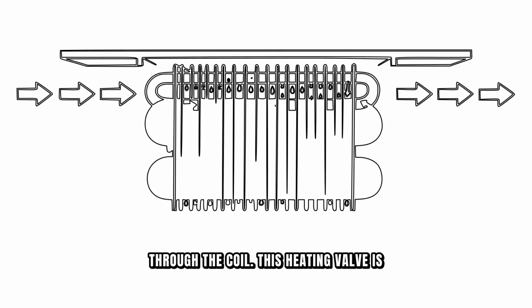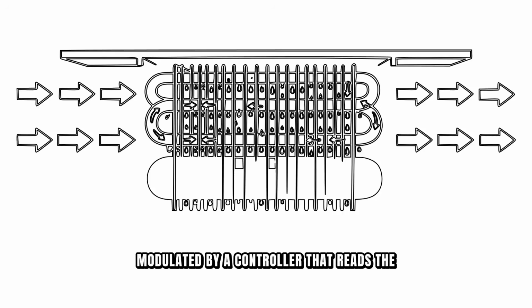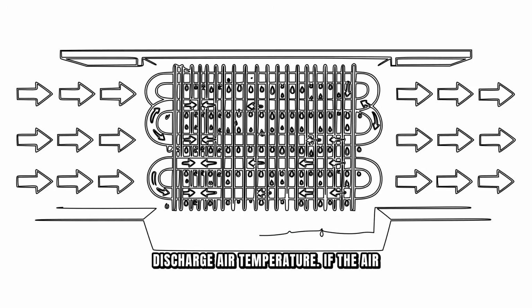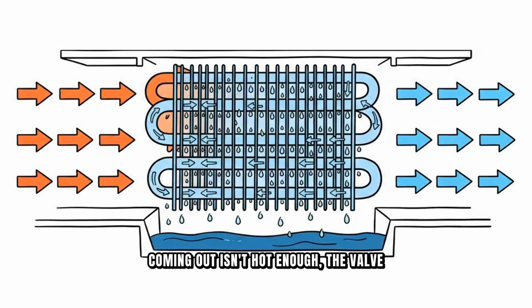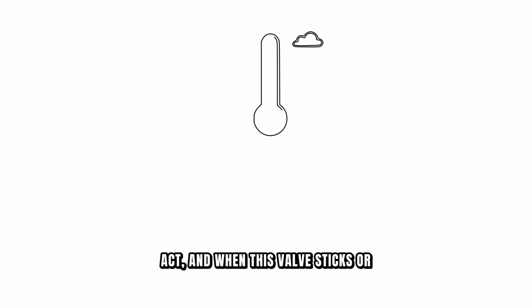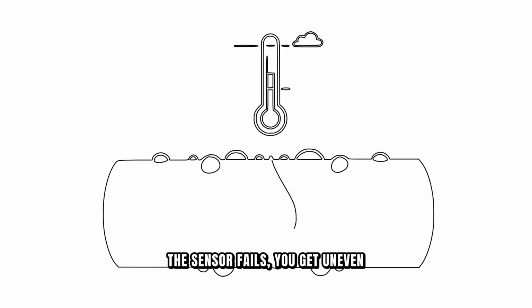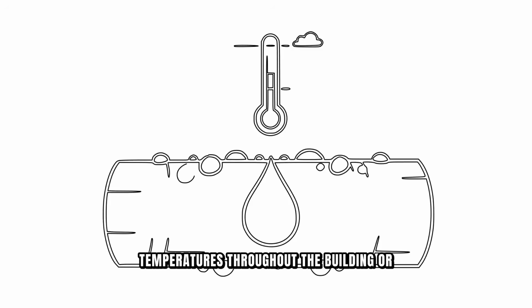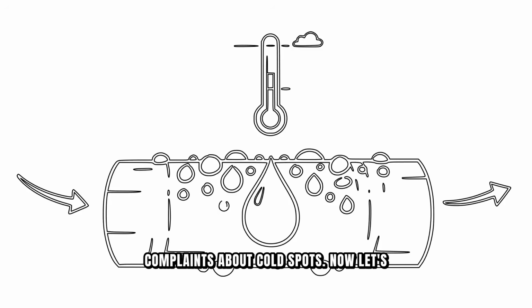This heating valve is modulated by a controller that reads the discharge air temperature. If the air coming out isn't hot enough, the valve opens more. If it's too hot, the valve closes partway. It's a continuous balancing act. And when this valve sticks or the sensor fails, you get uneven temperatures throughout the building, or complaints about cold spots. Now let's look at cooling.